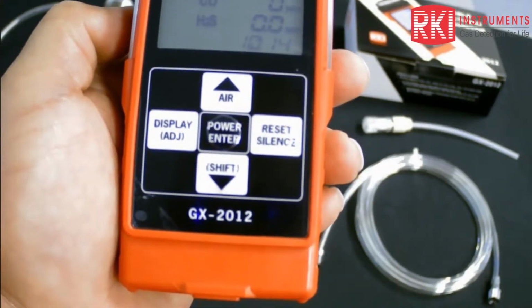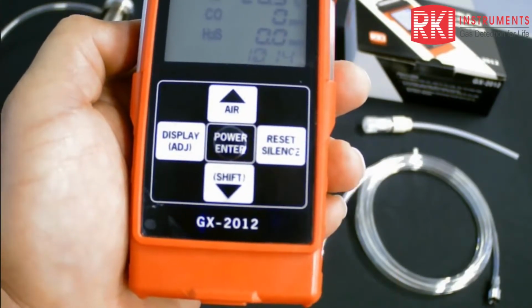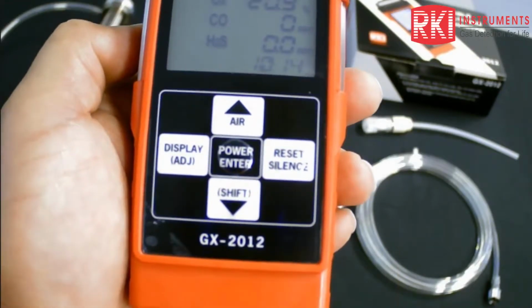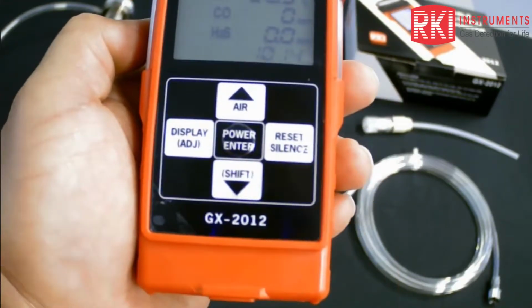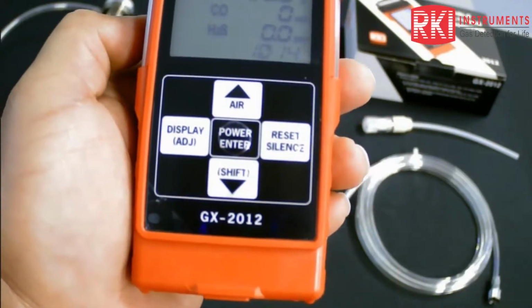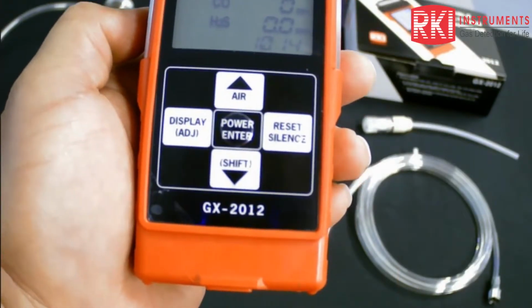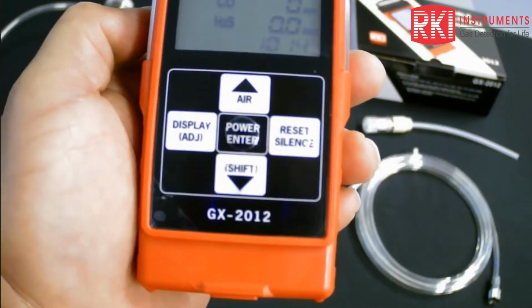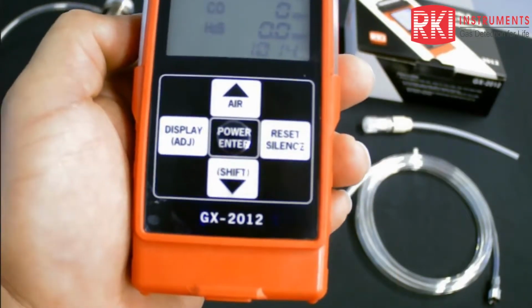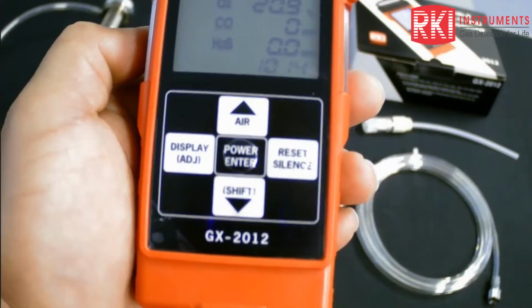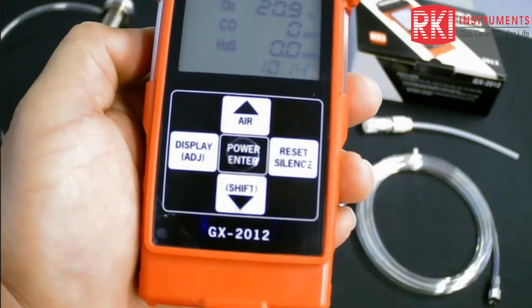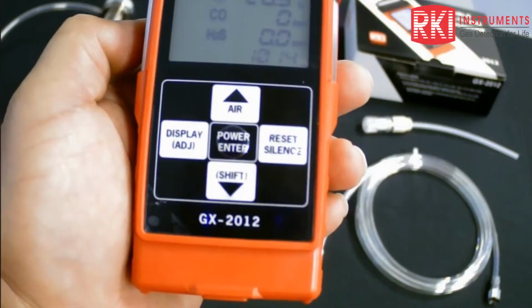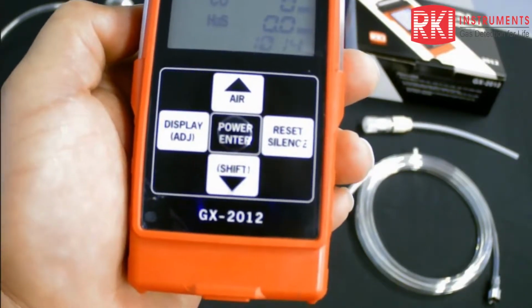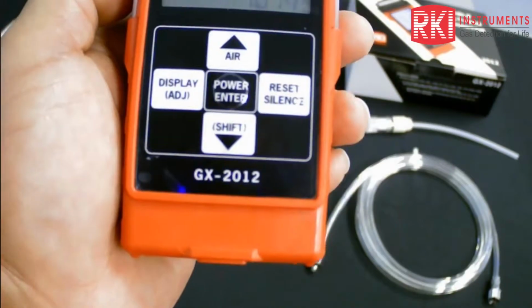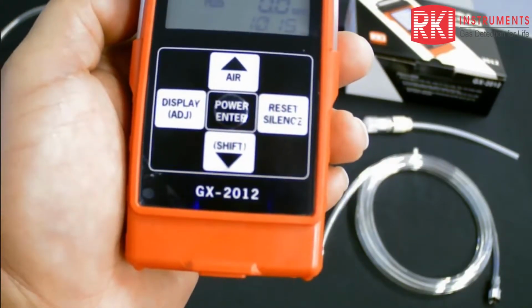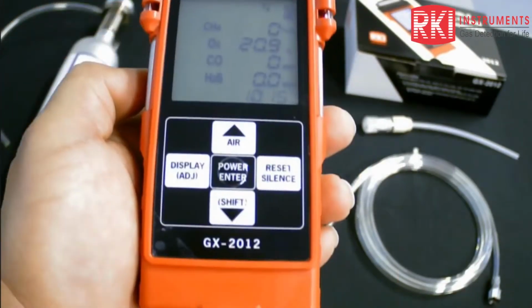So what we need to do is save that sensor and prolong its life as much as possible. Basically, if you have a lot of gas present and you have that fifth sensor on board, if you had a 4-gas standard unit, or let's just say the percent by volume sensor as well as that catalytic LEL sensor, then it automatically switches over. And when it switches over, the catalytic sensor shuts off and basically saves it from getting burnt out, so to speak, too quickly.